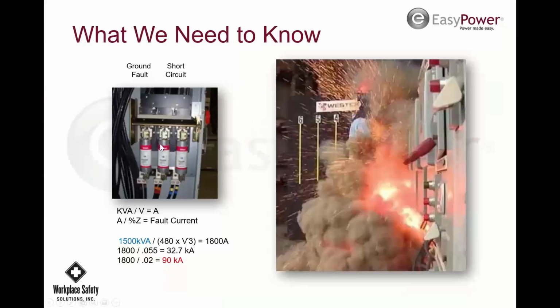So what causes it? It's either going to be a ground fault, and usually most of them start off with a ground fault. What can happen on 480 volts and higher is the air can become ionized. That means there's enough voltage, with a 277 volt system, to cause electrons to flow through the atoms in the air, and that creates a plasma, and that plasma turns to a three-phase fault, and then it blows into this big ball of fire. So that can happen when you have a fault that's a single phase. A short circuit is going to be phase to phase. The same thing will happen. It'll go to a three-phase fault.